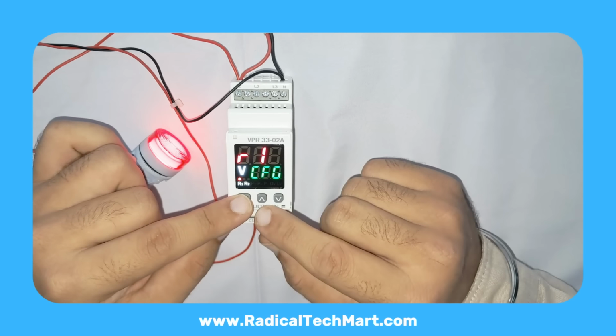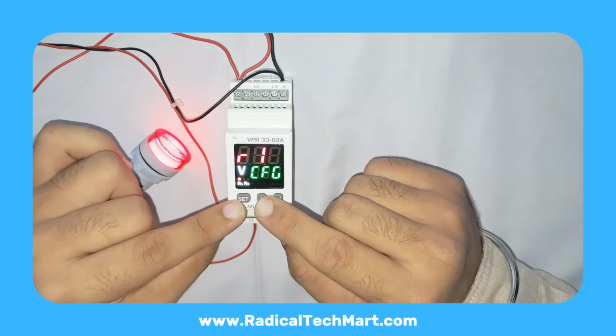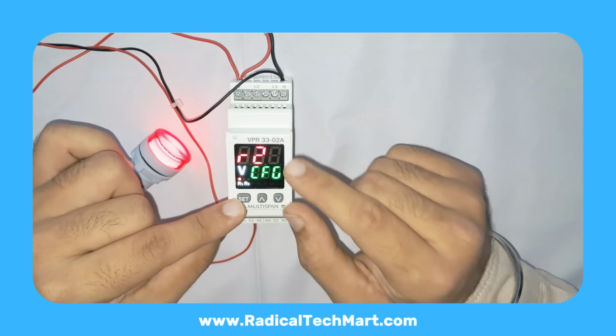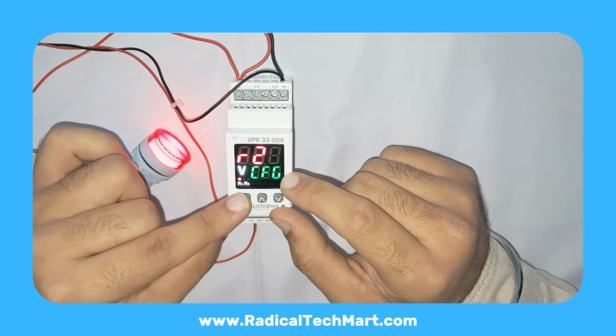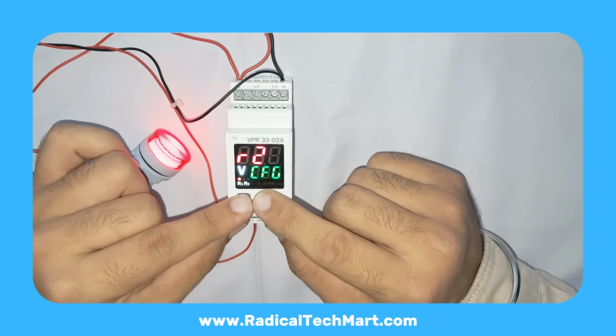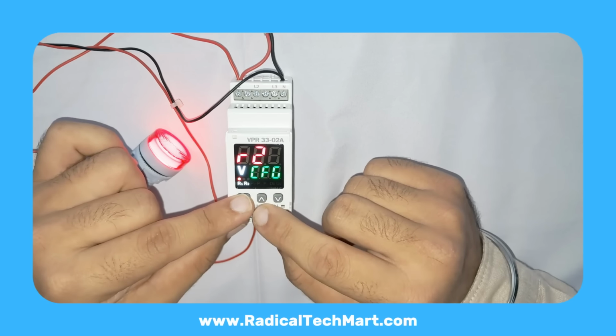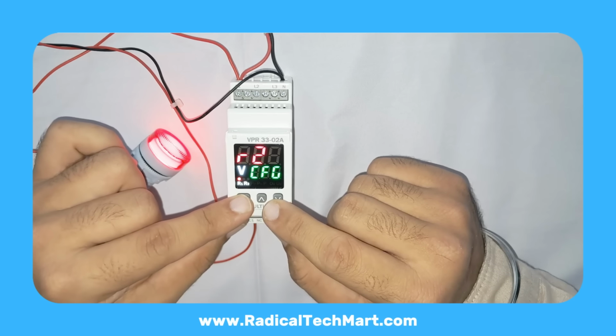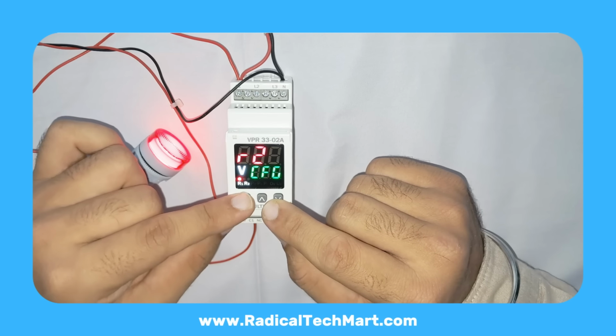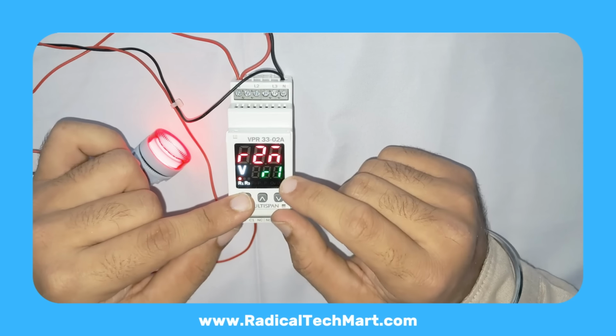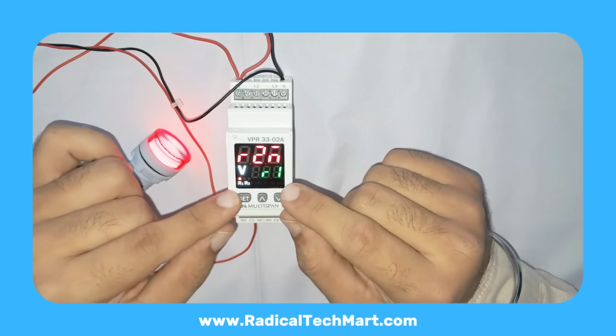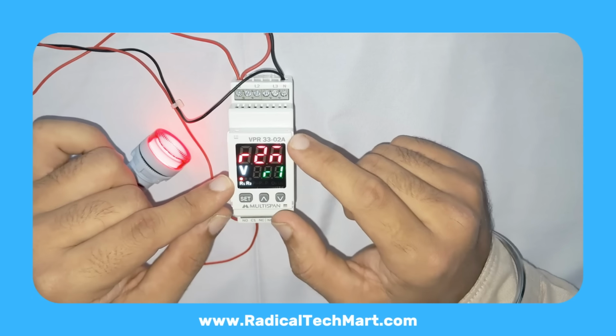Now you exit relay 1 configuration. Press the up button again. You will see R2 CFG, relay 2 configuration. The options inside R2 are exactly the same as R1. Overvoltage, undervoltage, overfrequency, under frequency, trip delay, reset mode, relay fault mode.